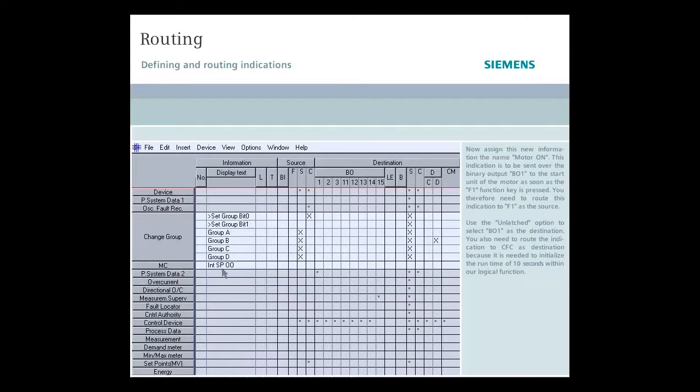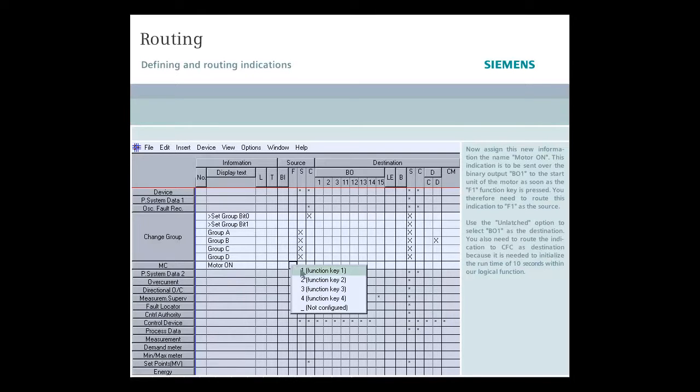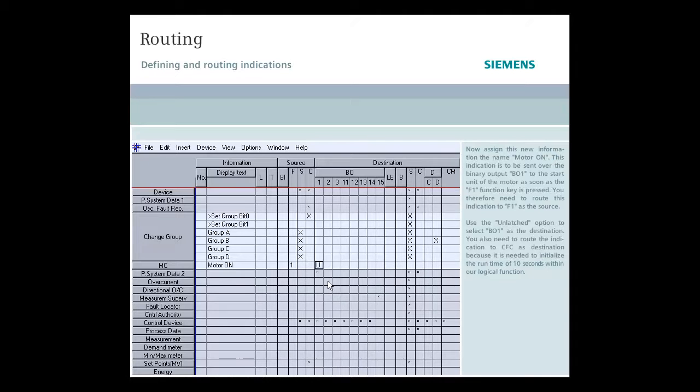Now assign this new information the name motor on. This indication is to be sent over the binary output BO1 to the start unit of the motor as soon as the F1 function key is pressed. You therefore need to route this indication to F1 as the source. Use the unlatched option to select BO1 as the destination.